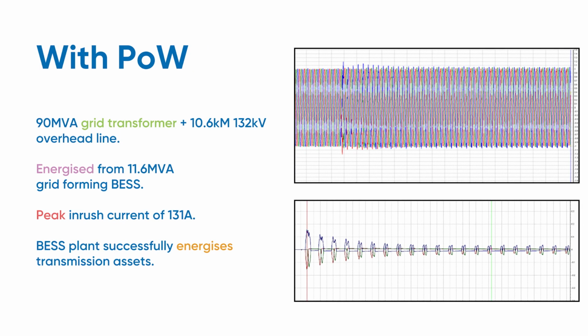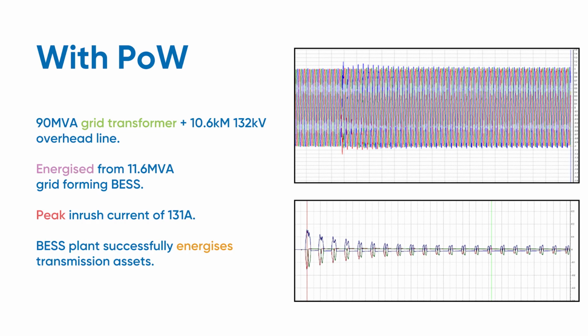So then we tried it with point-on-wave. Effectively, we've got the battery energy storage system. We've got a 33 kV circuit breaker that's now being controlled with point-on-wave to energize that 90 MVA grid transformer and the 132 kV overhead line. And as you can see, we massively reduce the initial inrush current. This means that the voltage instability is not seen anymore. The grid forming BESS is able to cope with this level of inrush current, and we get a sustained energization and successfully energize these large transmission assets from a very small anchor BESS.